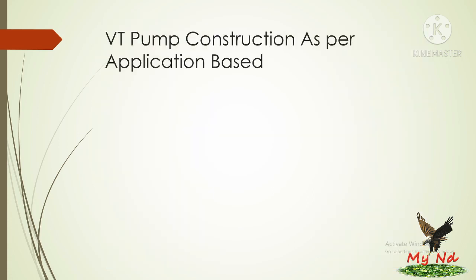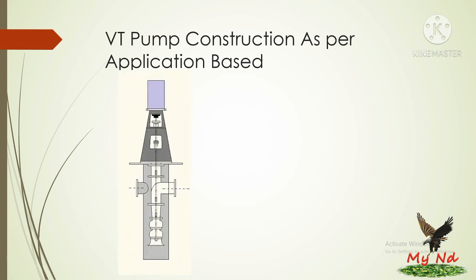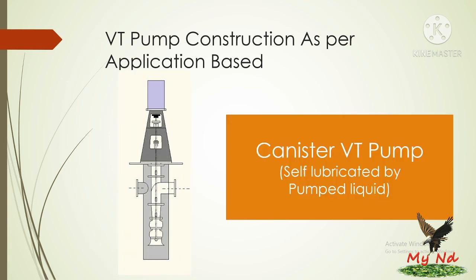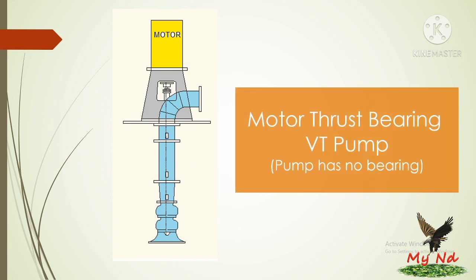VT pump construction as per application. Here is a picture of the canister type VT pump. It is self-lubricated by the pumping liquid. The pump has a canister, so it is called a canister VT pump. In another picture, we look at the motor thrust bearing VT type. In that type, the pump has no bearing. Pump setting depends on the motor thrust bearing, so it is called a motor thrust bearing VT pump.